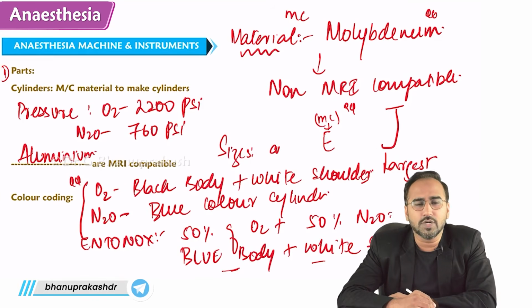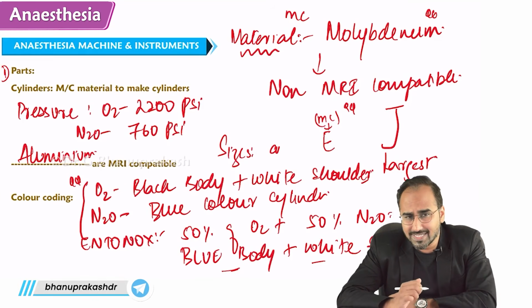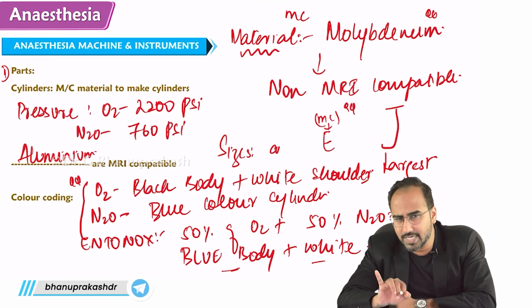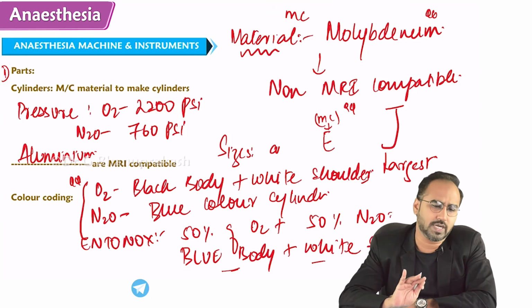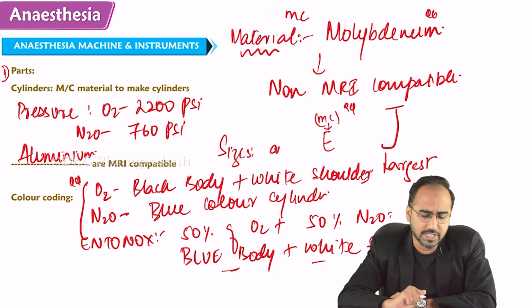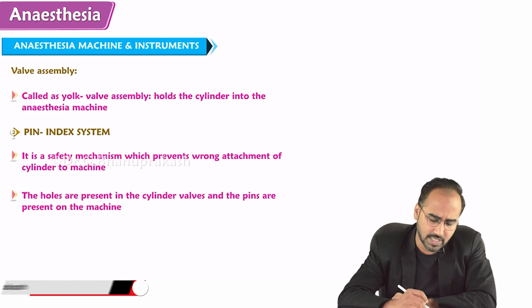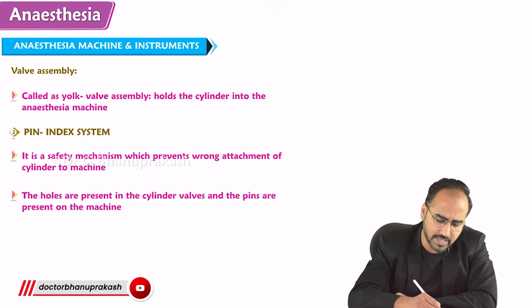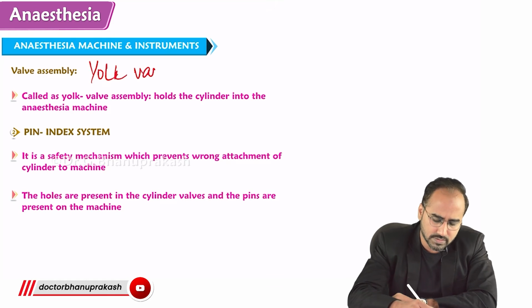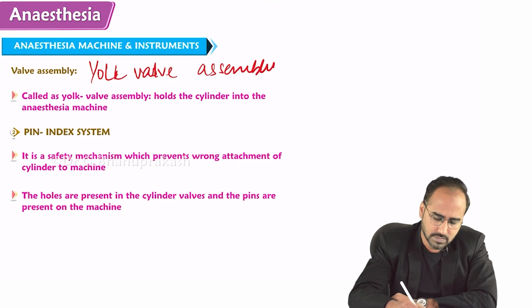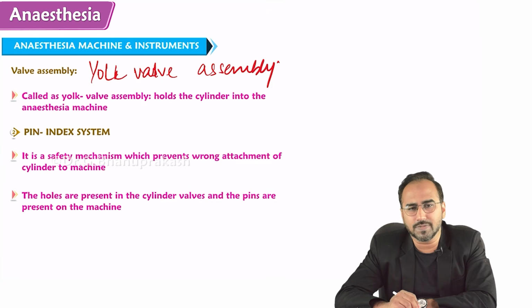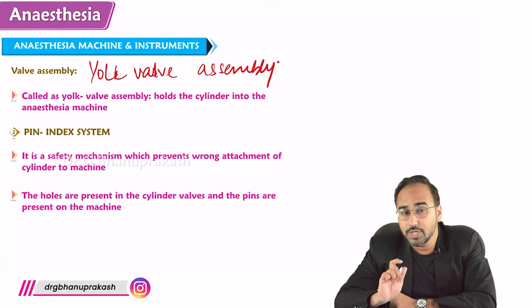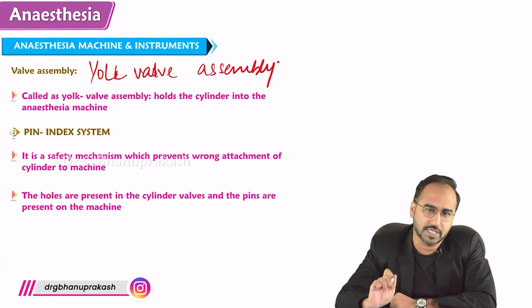Now, I told you how the cylinders are attached to the machine. But before going to how it is attached, remember the cylinder material, size and color coding. Next, how is the cylinder attached to the machine? The cylinder is attached to the machine with the help of a yoke assembly, called the yoke valve assembly. The yoke valve assembly holds the cylinder to the machine.